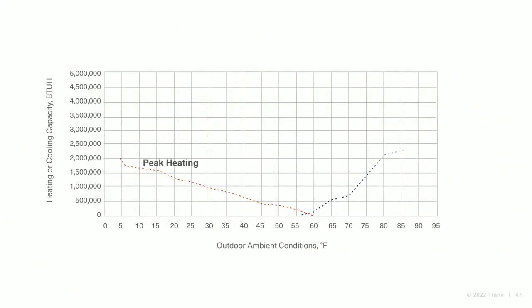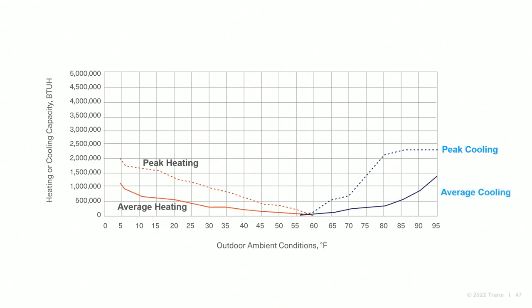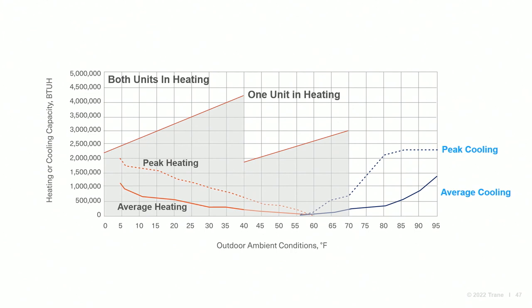Here is what sizing the heat pump plant with two 200-ton heat pumps would look like across the entire year. The dashed lines are the expected peak loads for the ambient temperature, and the solid lines are the average plant load for the ambient conditions. Between 40 and 70 degrees, we assume one heat pump is dedicated to heating mode and the other is dedicated to cooling mode. Shown here is heating mode with the capacity derate as the ambient temperature decreases. Below 40F, both units are in heating mode. Including the defrost derate, we can see we still have adequate capacity to meet the design heating peak.